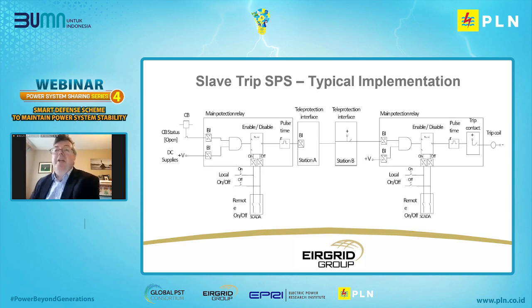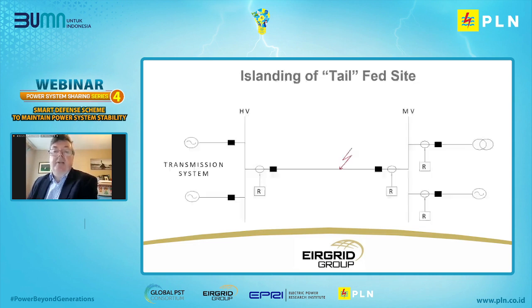Then that's picked up at the teleprotection interface at the remote end and fed into the relay again. So again, if the DC supply is healthy, the receipt of that signal goes into the enable disable logic, and again it's into a pulse timer. And so if it's enabled, the trip contacts are commanded momentarily to open the breakers. So that's just one example of how it's actually implemented. Okay, so next slide, please.